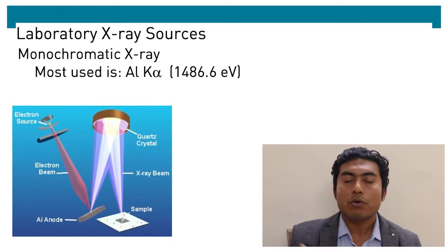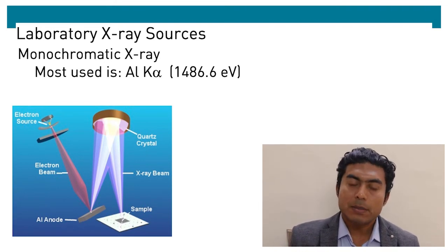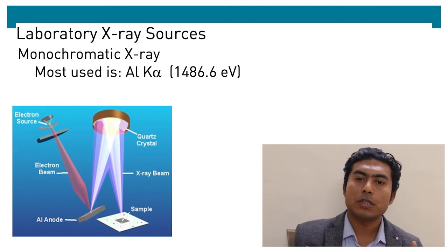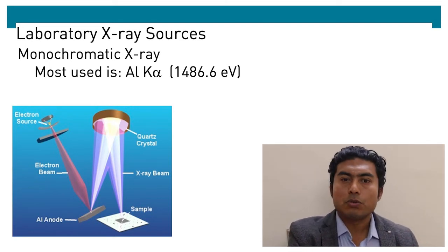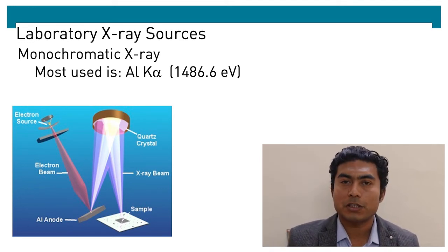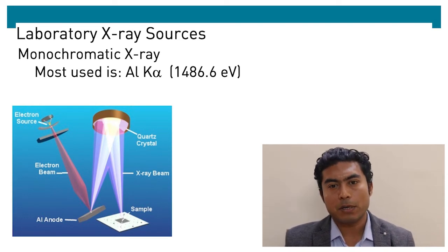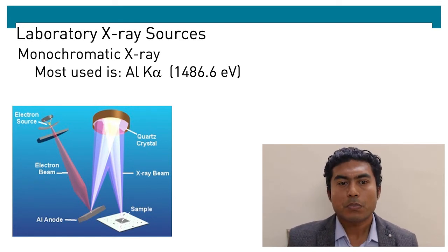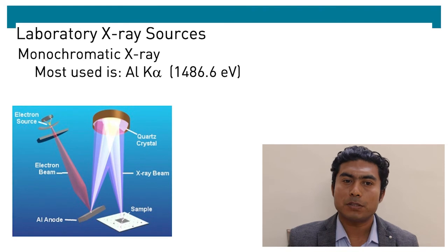For narrow or wavelength-selected X-ray radiation, we use monochromators. In the monochromatization process, we use quartz crystals to choose a particular wavelength from the characteristic X-ray broad range to shine on the sample. The principle of Bragg's diffraction applies here. The X-ray source, the crystals, and the sample all align in a Rowland circle. You can refer to the reading materials to learn more about this process.